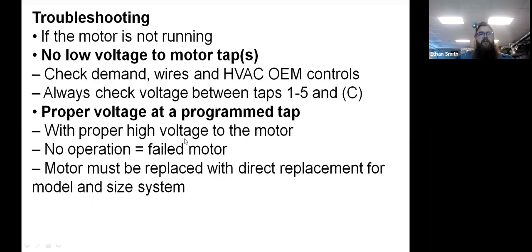Let's check for proper operation. So again, this motor is a frequency driven motor. And so it has 120 volts powered to it all the time. So you're going to check for a high voltage source and you're going to check for a low voltage signal on these motors. If you have both of those things and the motor runs, the motor is good. If it doesn't run and it has both of those things, the motor is bad.